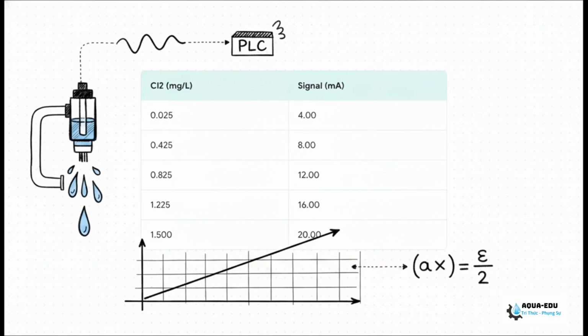This translates directly into the formula your PLC uses. Concentration equals the current minus 4, divided by 16, multiplied by the span of 1.475, plus the base of 0.025. Verify this math is perfectly mirrored in your PLC programming.